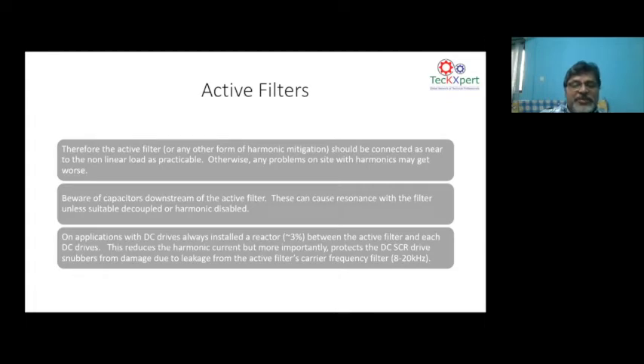Similarly, for your drive systems, you should always ensure that there is a 3% line reactor at the input of the drive, so that the harmonic overloading does not take place for the active filter.